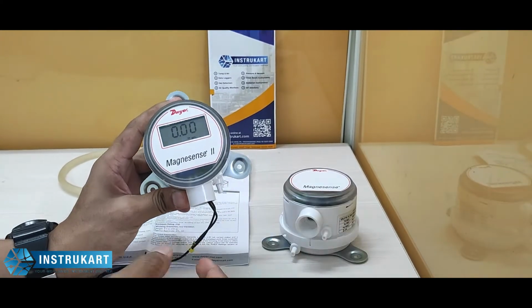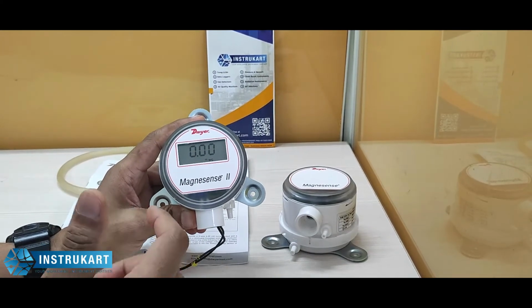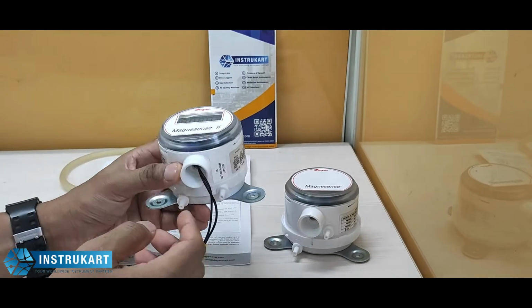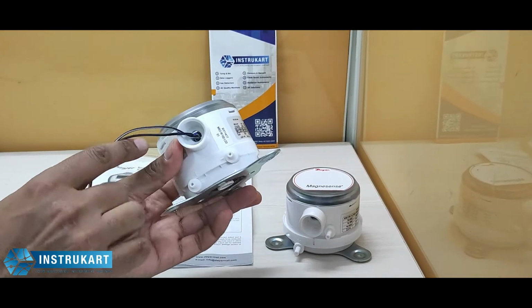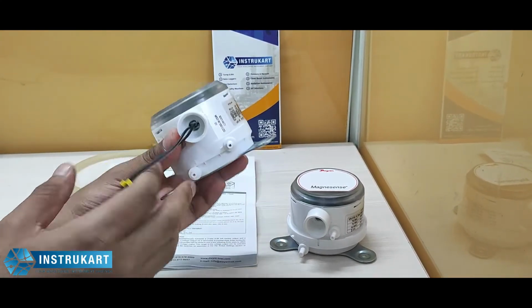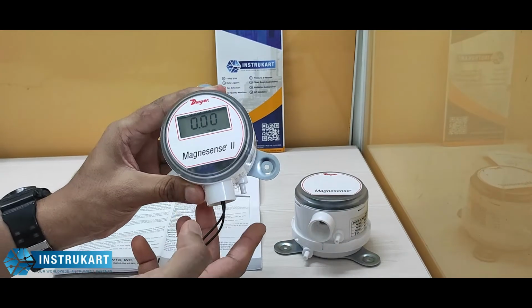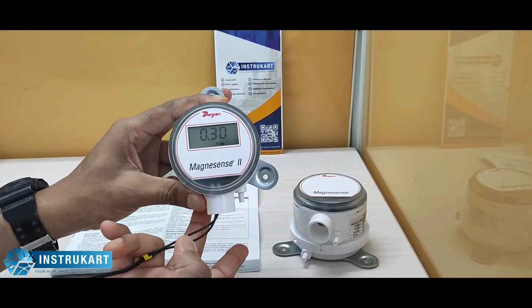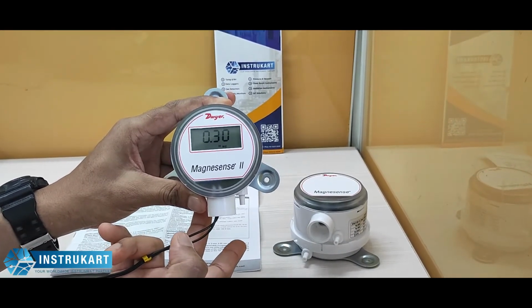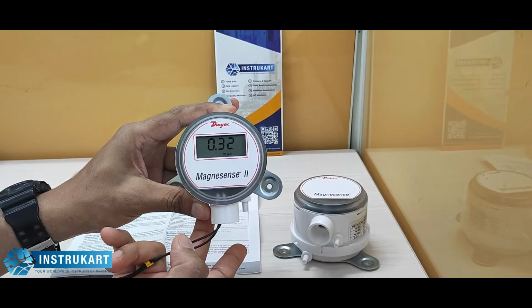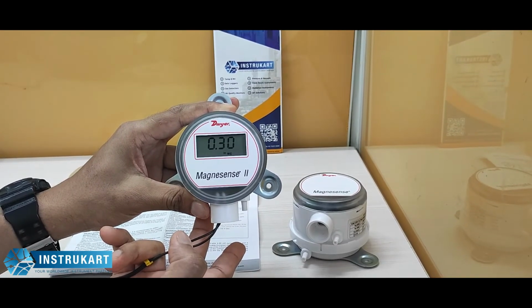Before ordering, you need to be sure about the part number which you are ordering for the measuring range. Now these are the points where you will be extending your tubes for the minus and plus differential. If you want, you can put your finger to check if the inches of water column is having a different measurement.